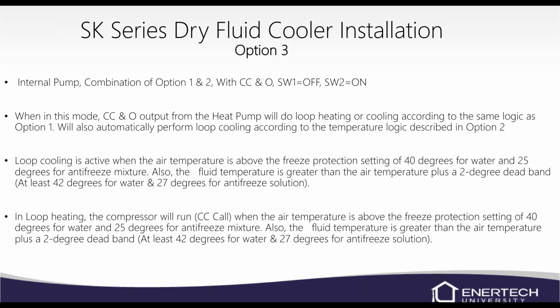Option 3. So now you'd have a combination of option 1 and 2, which is switch 1 off, switch 2 on. Basically, when in this mode, the O signal output from the heat pump will do loop heating or cooling according to the same logic as option 1. Basically, which will automatically perform the loop cooling according to the temperature logic, again, based on your 40 and 27. Loop cooling is active when the air temperature is above the freeze protection setting. Also, the fluid temperature is greater than the air temperature plus your 2 degree deadband, so just like option 2.